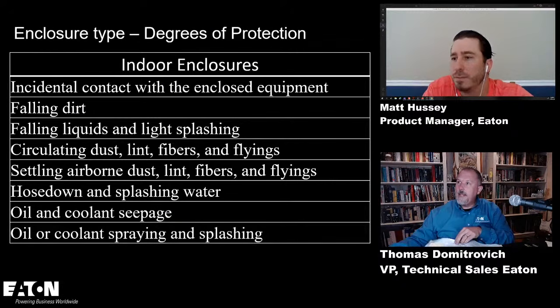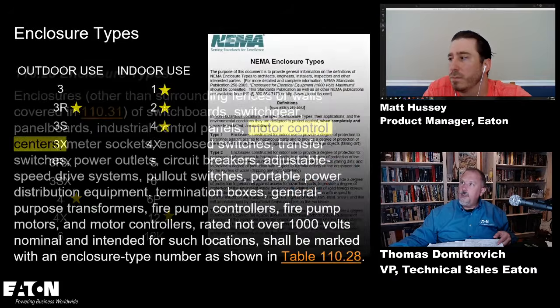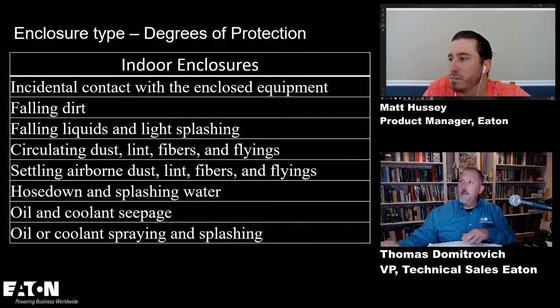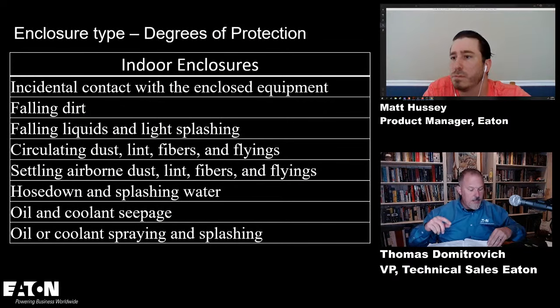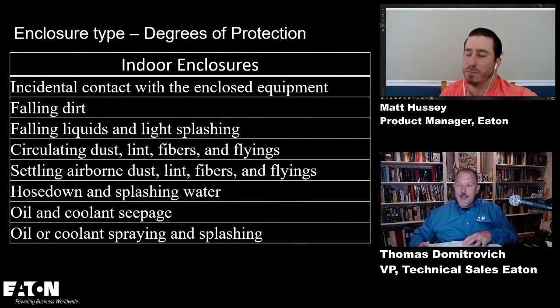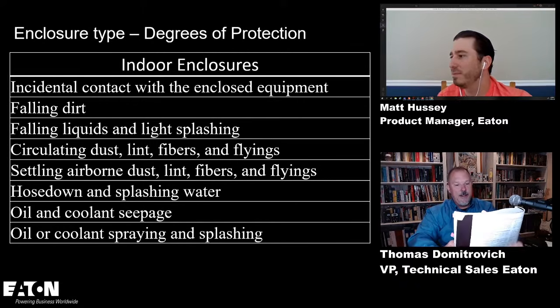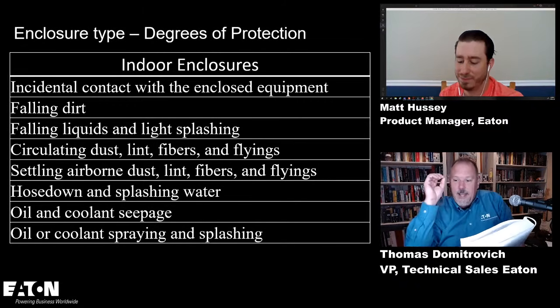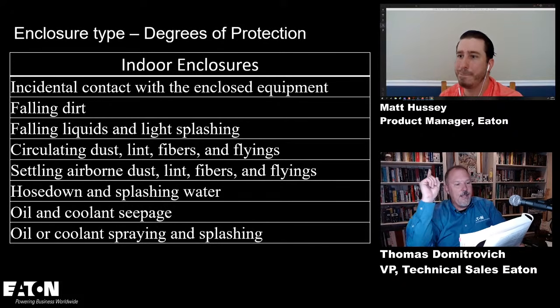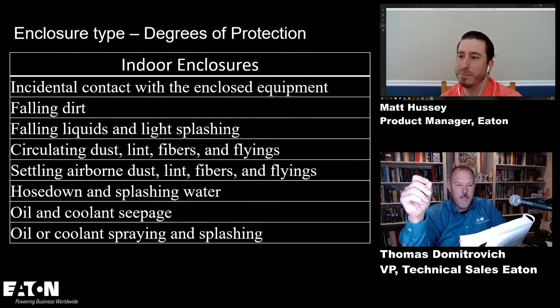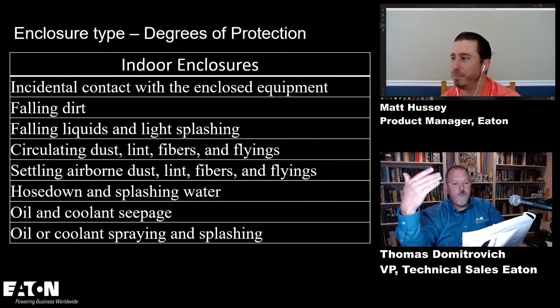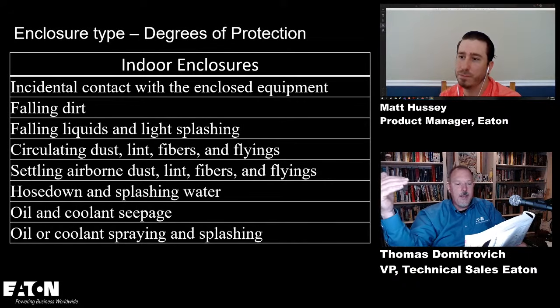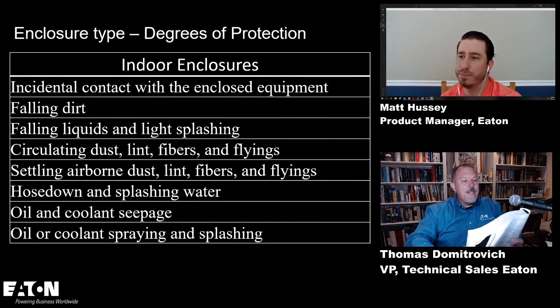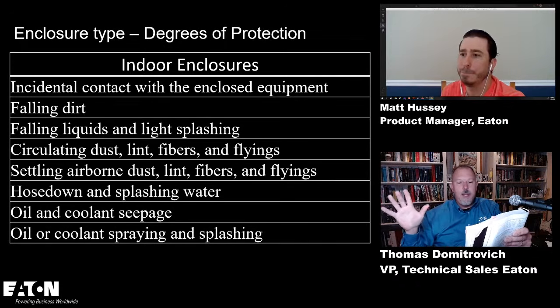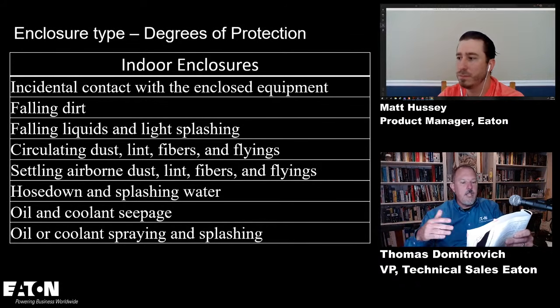And so what I did here was I went through section 110.28, which is enclosure types. And if you look at 110.28, there's a table in there. I'm glad we got guys like Don Ganier on the phone on this one as well, because I'm going to ask a question, Don and Ryan, and Felix and Mr. Abbasi. Okay, so 110.28 says enclosure selection, and there is a table in there for outdoor use and for indoor use. What I did here was call these the degrees of protection, right? So incidental contact with the enclosed equipment, that's the basic fundamental, and every enclosure gives you that. Rain, snow, and sleet, every enclosure gives you that. This is for outdoor use.